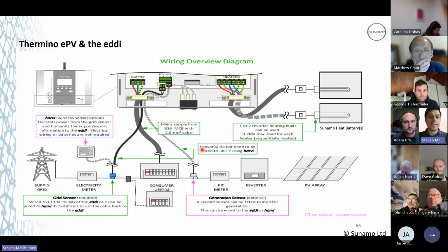So our eddi, you could potentially fit 2 batteries to an eddi. So obviously heater 1 we go into L1 and N1. That'd be your priority battery, and then obviously the secondary one. With that configuration, we'd recommend having it plumbed in series. So if you think about your outlet battery, so obviously you've got 2 batteries, you've got an inlet going into your first battery, and then your second battery's got your outlet. Your outlet battery, that's going to be your priority battery. So you'd have to wire your outlet battery into L1 and N1, and your secondary battery would be your inlet, and that would be L2 and N2.